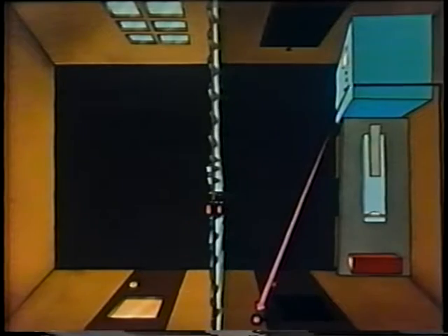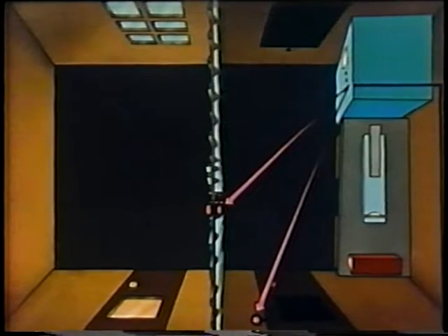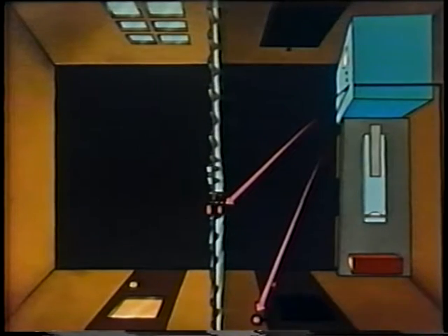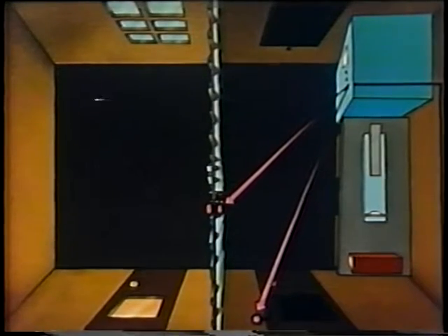The laser system should be isolated from any other activity in the room with a safe partition, such as a blackout curtain or folding screen. All windows and door windows should have blackout curtains or some other absorbent material. Safety interlocks should be provided for all doors, the primary entrance and the secondary entrance, such as the isolating screen. The interlocks are connected to the power supply.